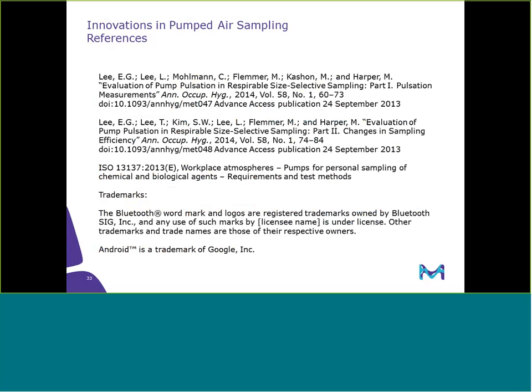I'm going to tell you to speed up or slow down to stay at whatever flow rate you have me set at. So when you hook it to your sampling train, sampling trains are all going to have various back pressure numbers depending on what you're hooking to, whether it's a cassette or an Orbo tube or some other type of media, a cyclone sampler or anything like that. They're all going to have very different back pressures, and those back pressures are going to have an influence on the sampling pump as far as trying to maintain flow rate. So the calibration device sees what flow rate is coming through your sampling media and into the pump, and it says, you are not operating at what you set me at, so I'm going to speed you up or slow you down and adjust you to get that flow rate.